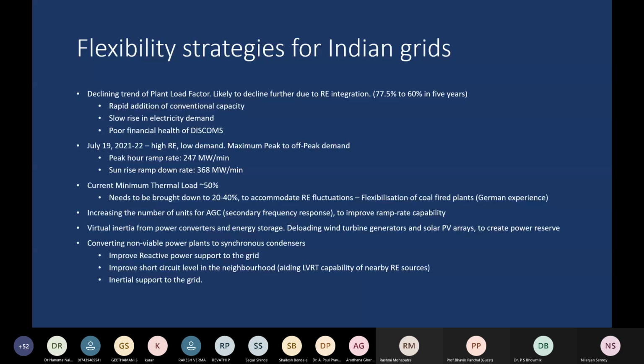We need to come up with some sort of a frequency response, and that is actually going on. POSOCO is looking at ways to increase AGC, the number of units that can be put on AGC, automatic generation control, so that the network frequency is supported in the event of a sudden drop or rise from the wind or the solar farms. So one of the ways that this could be done is using energy storage.